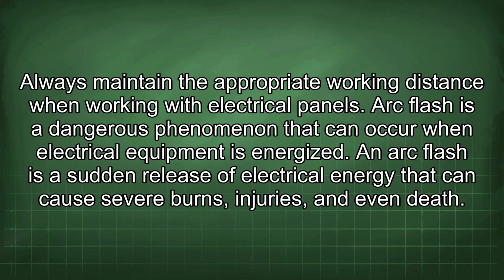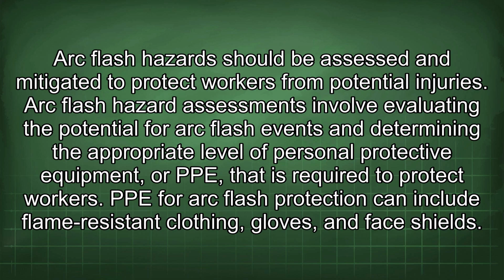Arc flash is a dangerous phenomenon that can occur when electrical equipment is energized. An arc flash is a sudden release of electrical energy that can cause severe burns, injuries, and even death. Arc flash hazard should be assessed and mitigated to protect workers from potential injuries. Arc flash hazard assessments involve evaluating the potential for arc flash events and determining the appropriate level of personal protective equipment, or PPE, that is required to protect workers. PPE for arc flash protection can include flame-resistant clothing, gloves, and face shields.